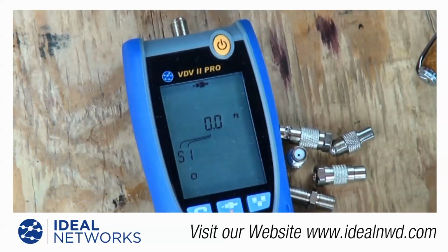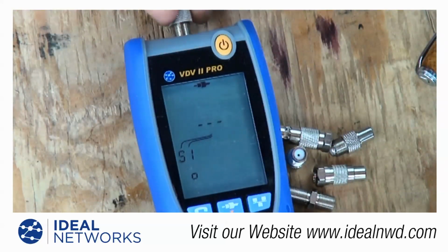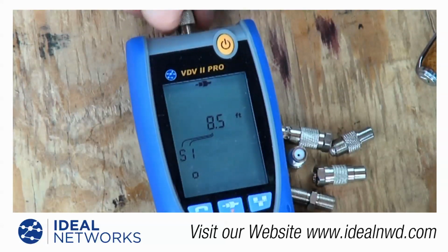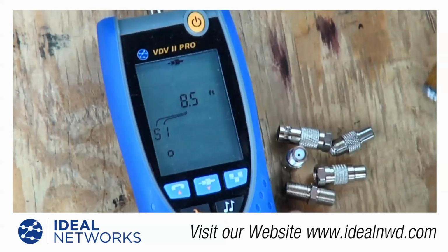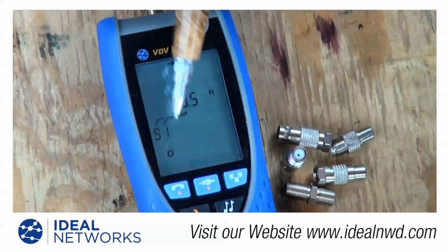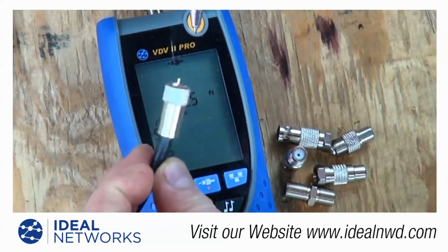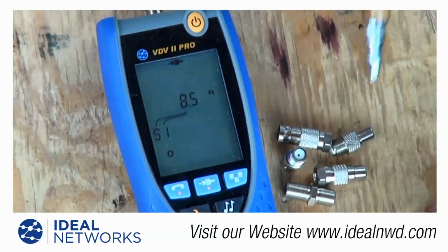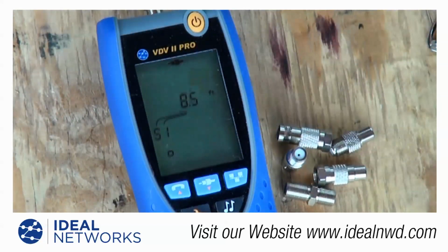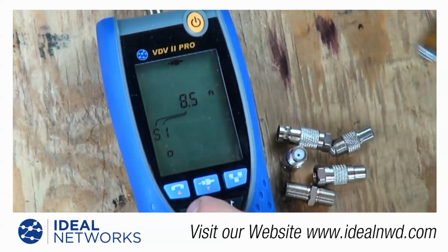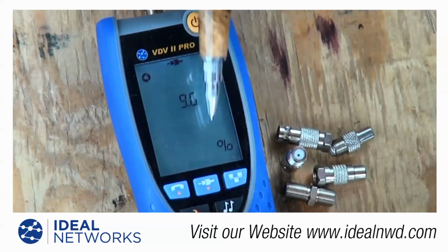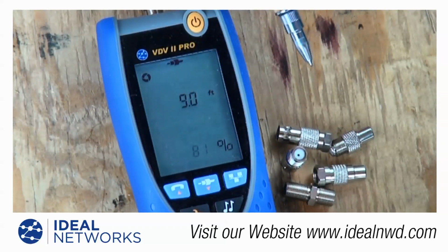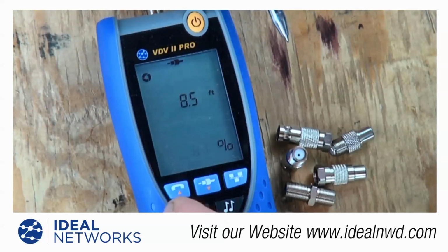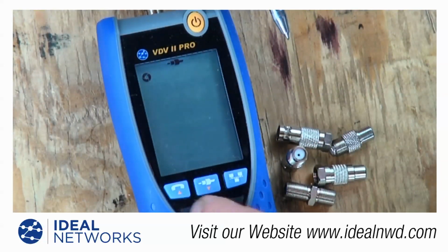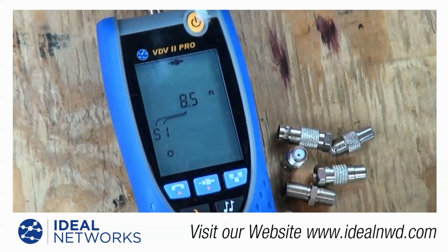Typically when you work with F connectors, we're going to plug a cable into the top of the tester. And when I do that, the tester automatically sees a cable. It sees an open in the cable because there's nothing connected to the other end of this cable. And it sees about an 8.5 foot long cable. Okay. Now, that length measurement, keep in mind, I could adjust by going to the tool section and changing the nominal velocity of propagation of a particular cable. In this case, it's set at 81% and shows me about 8.5 feet.